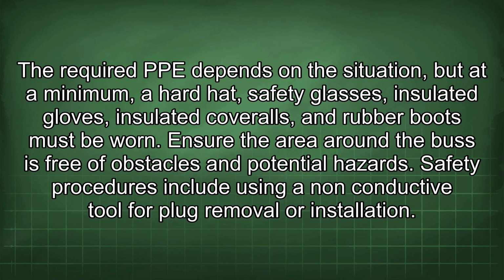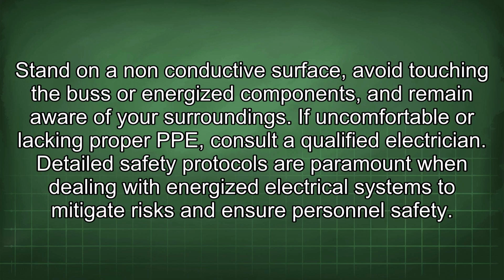Ensure the area around the bus is free of obstacles and potential hazards. Safety procedures include using a non-conductive tool for plug removal or installation. Stand on a non-conductive surface, avoid touching the bus or energized components, and remain aware of your surroundings. If uncomfortable or lacking proper PPE, consult a qualified electrician. Detailed safety protocols are paramount when dealing with energized electrical systems to mitigate risks and ensure personnel safety.